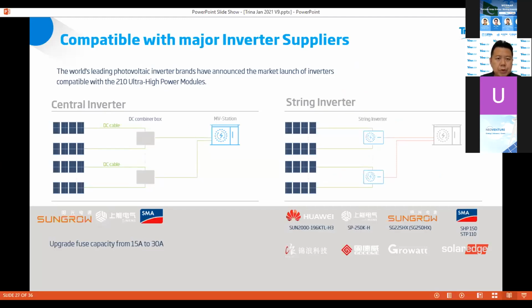On top of this, we also get a lot of questions or concerns on how these high current modules can match with inverters. On the left here is a central inverter. We have worked with the major inverter suppliers on the central inverter, so there's no problem being compatible with the Trina Vertex module. In terms of system design, the fuse capacity has to be upgraded from 15 amperes to 30 amperes. On the right is the string inverter. We have also worked with major inverter suppliers on string inverters. All these suppliers will have compatible models coming to the market in the next 1 to 2 quarters.